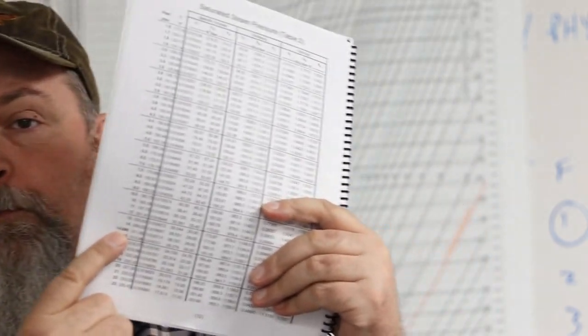Now, let's say you don't know the temperature, but you know the pressure. Well, you go to table two. Table two gives you the pressures that correspond to all the stuff. So if we go find 14.696 PSIA, 14.7 pounds absolute, that corresponds to 211.95 degrees Fahrenheit, so 212 degrees Fahrenheit.